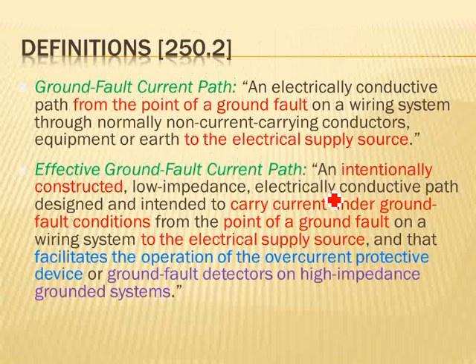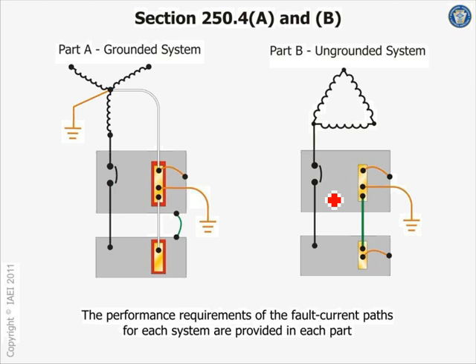This is how they define a ground fault path, from the point of the ground fault all the way to the electrical supply source. This is so important. So if I have a ground fault in this fixture, the ground fault path is from here all the way to the service, where the transformer bringing power is. An effective ground fault path has to be large enough to facilitate the operation of the overcurrent device. Talk about this one. Can you guys see, here's my grounded system, ungrounded system. Look and see, it's identical.